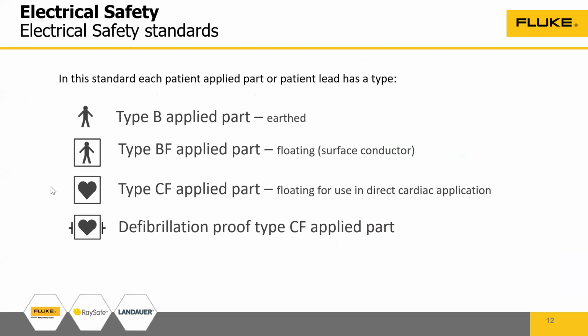Apart from that, all medical devices are again classified based on the kind of applied parts they have. Applied parts are the parts which are connected to the patient. Suppose in an ECG machine, the ECG electrode is an applied part. Even a pulse oximeter's SpO2 sensor is an applied part. A defibrillator paddle is an applied part, which directly gets connected to the patient. So based on the applied parts, it is again classified.